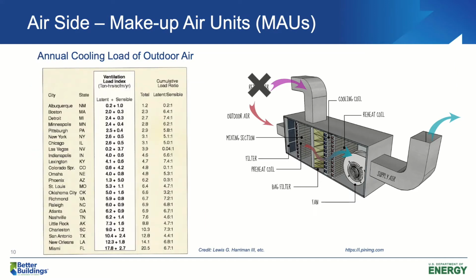This table shows you the annual cooling load per CFM of outdoor air for various locations. For example, at Miami, Florida, the total cooling load per CFM is about 20.5 ton-hours. That includes both sensible and latent heat. For Oklahoma City, Oklahoma, the total cooling load is less, which is about 6.6 ton-hours per CFM per year. But for Boston, Massachusetts, the cooling load is even less, which is only 2.3 ton-hours per CFM per year. This table also shows the sensible and the latent cooling loads separately for these locations.